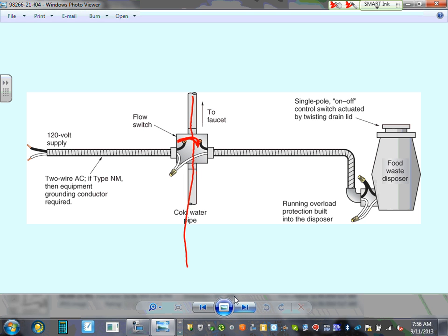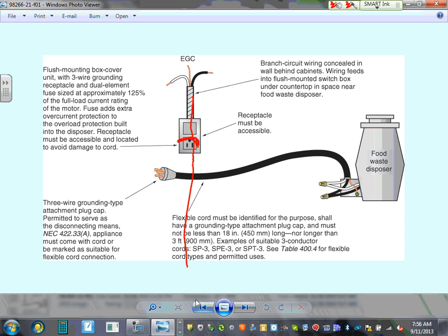But a flow switch is basically, the water goes in here, inside the pipe. As the water moves in, it physically, mechanically pushes two contacts and closes them through the action of water. You know, there will be something inside the water. So now, if you do it this way, you guarantee that your garbage disposal will never run unless what? Unless the water is running. So that's one way of doing it. So the garbage disposal is always guaranteed water. Any comments, guys? Any questions about the garbage disposal and the dishwasher?